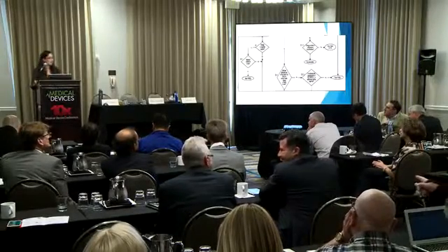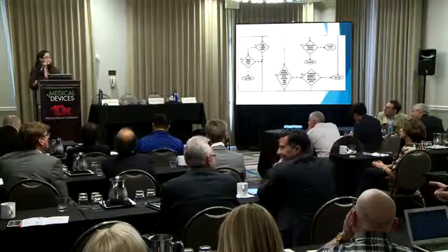You need to find a predicate or wait until there's another predicate device. I mean, it sort of doesn't make sense. No, I've used predicates that are long dead, that don't exist anymore, but I know their formulation. Let's say it's a resin that I know is exactly what the device was, and we'll test against it. Or say, the materials in our device are identical to what was cleared in that device.